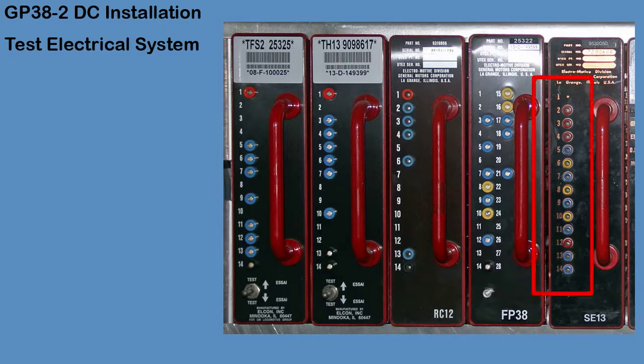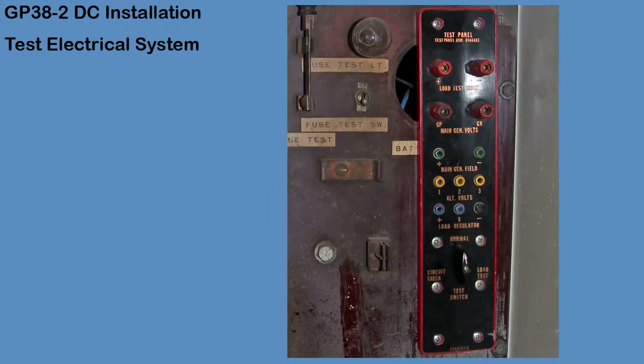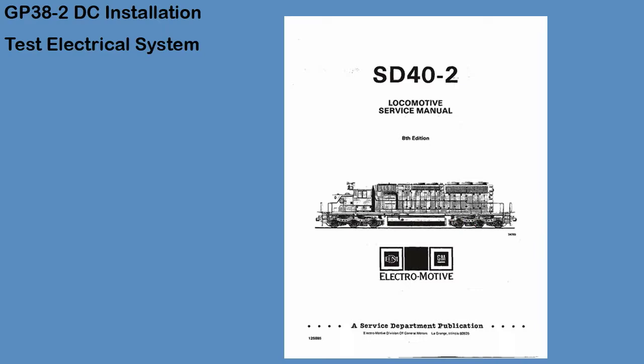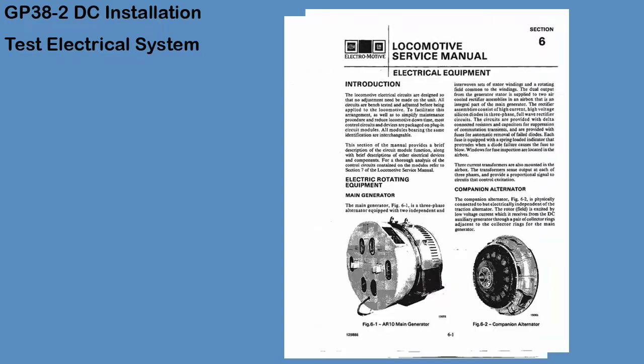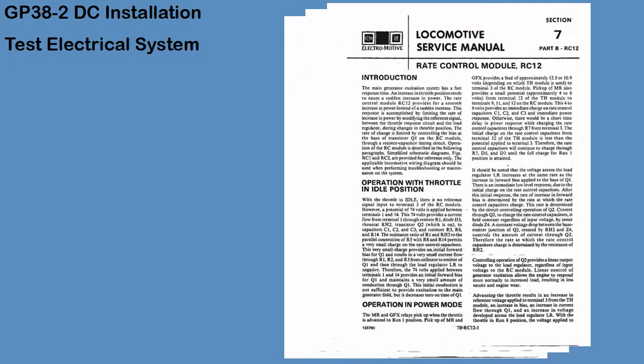Test points mounted on the faceplate of the -2 modules provide easy access for taking measurements. Some modules also provide a test switch. The switch function is module dependent, but usually it is used to verify a specific control function within the control system. In addition to the -2 modules, the load test panel also provides test points and a test switch, again used to select specific test functions. More detail is provided in the widely available -2 service manual, which contains sections on the electrical equipment and separate sections for each of the -2 modules.